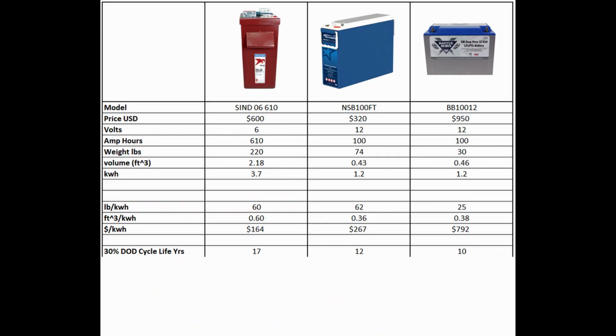Assuming your float voltage is set slightly below what's recommended by Battleborn, this means that 10 years should be achievable. And when I say float voltage, I recognize that lithium batteries don't require a float, but in reality, generally, you have a float voltage. Thus far, we see that lithium seems to be getting crushed by the competition. It costs more per unit capacity, it takes up the same amount of space, it doesn't last as long as lead-acid options. The only advantage that we've identified is still weight.